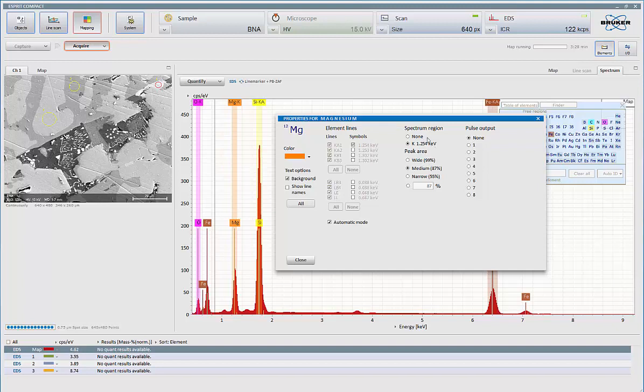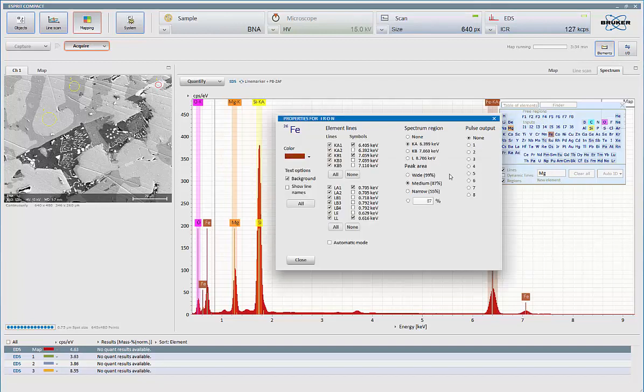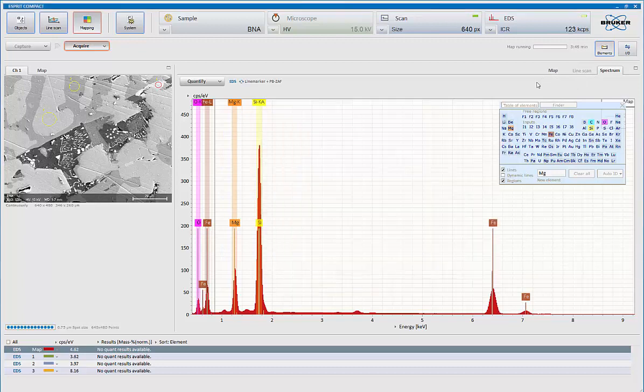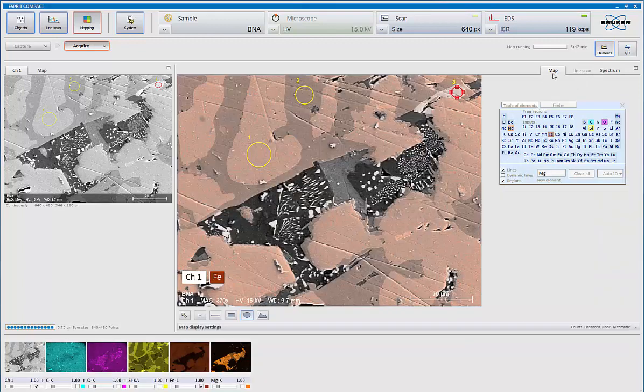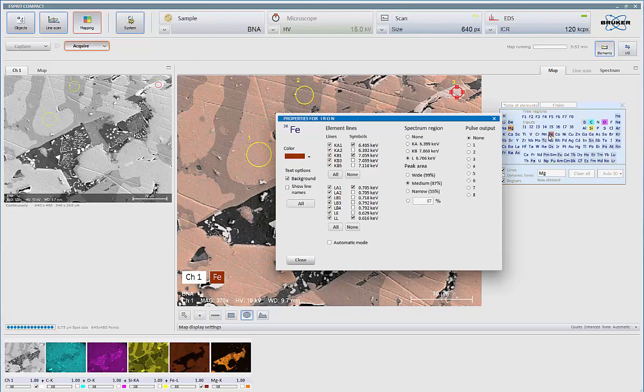The system also, if I have a choice of multiple lines, will let me select them here. So in the case of iron, I could elect to look at the iron K-alpha, the K-beta, or the L-line. And as soon as I click on it, the map would be changed from the K-line to the L-line. So if I go to map now, now we're looking at the map based on the iron L-line. And again, you can change that at any point in time.